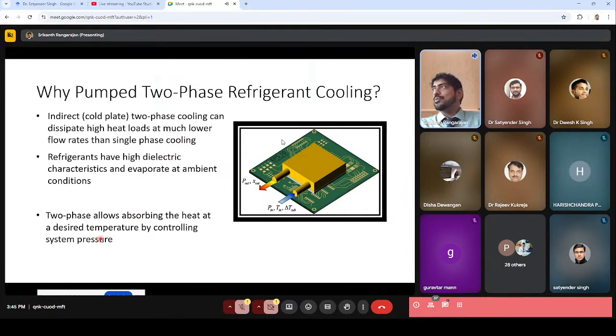The dielectric fluids often have a saturation temperature that is a function of the system pressure. So if you're able to regulate the system pressure, you can regulate the saturation temperature depending on the temperature required by your device. For example, if you want to regulate your device temperature to 60 degrees Celsius, you can choose the fluid and regulate the system pressure so that the saturation temperature is closer to 60 degrees Celsius, allowing you to absorb most of the heat at that temperature.